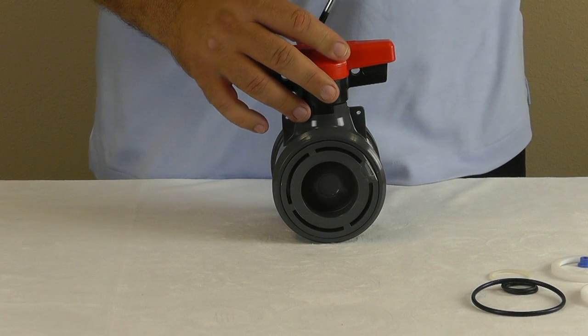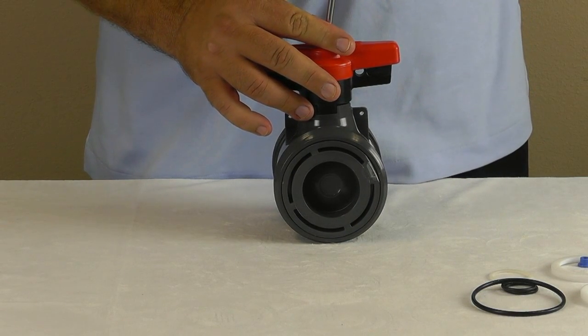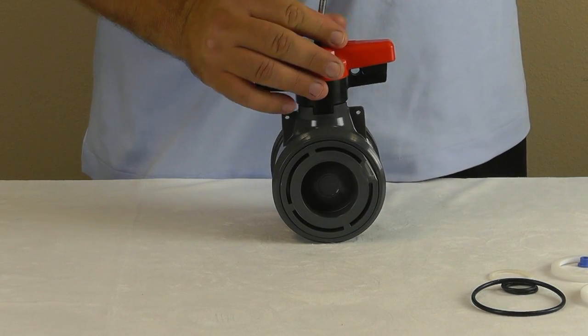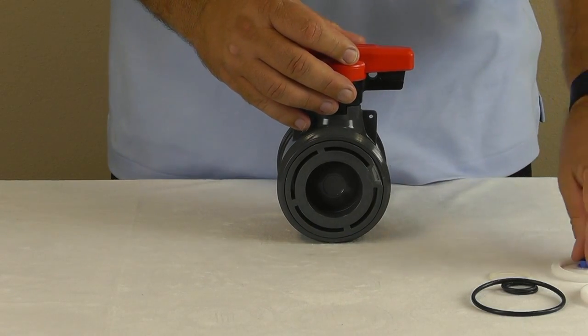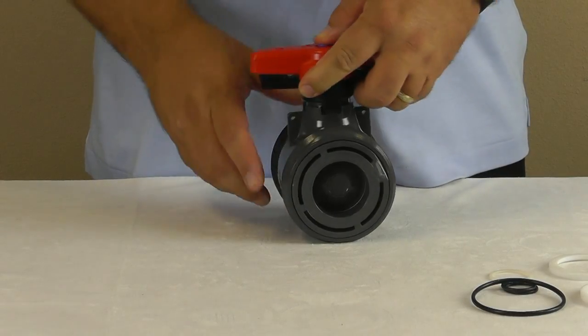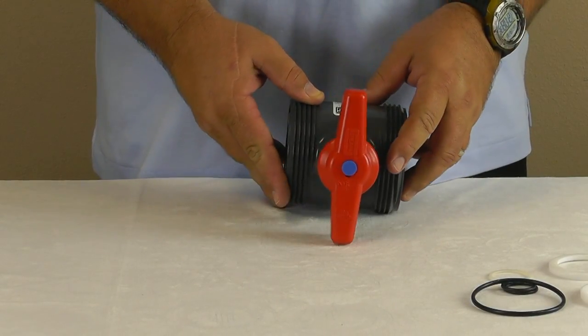Open and close the valve. If you don't feel a positive resistance when closing, cycle the valve and adjust the seal carrier until resistance is felt. Do not over-tighten the seal carrier. This may bind up the ball and not allow open and close cycling.